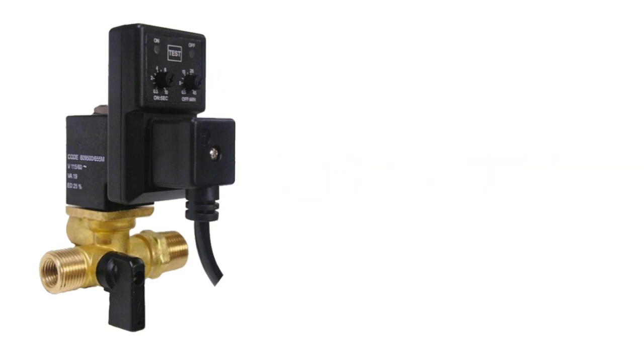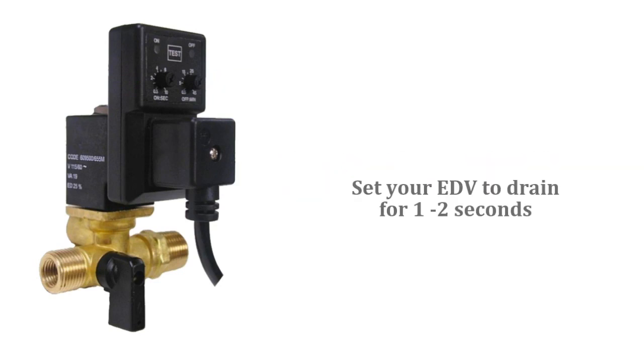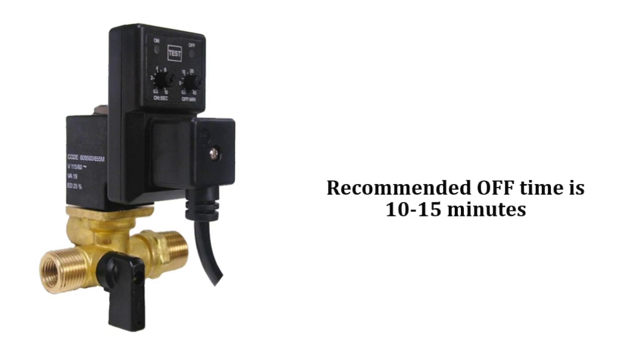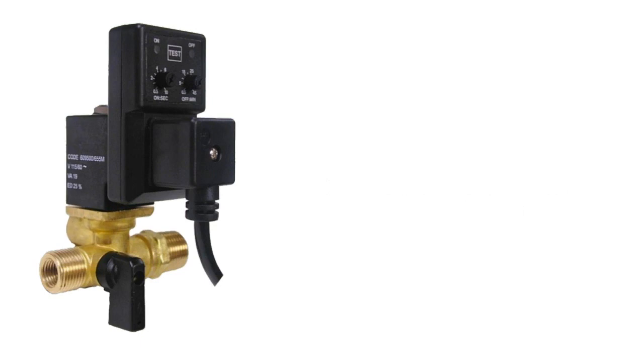Set your EDV to drain for one to two seconds. The recommended off time is 10 to 15 minutes in a typical air system. Reduce the off time if you have more water in your system.